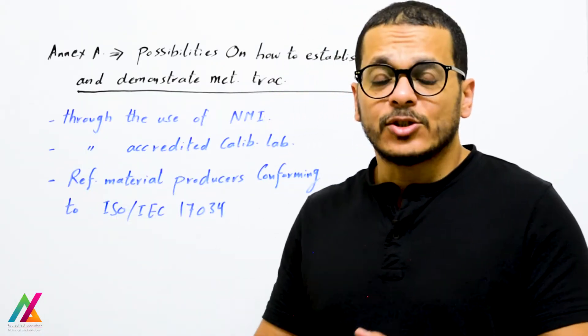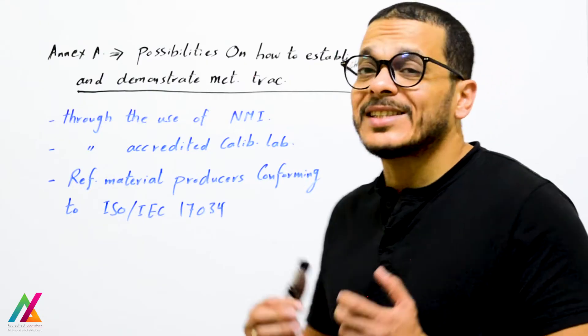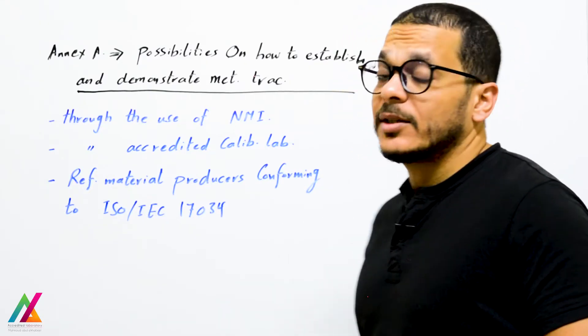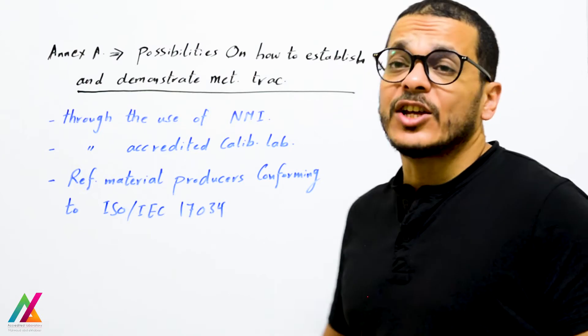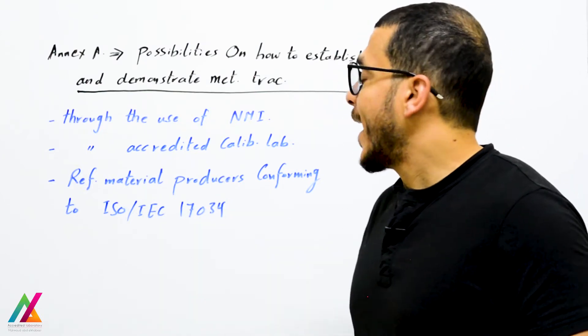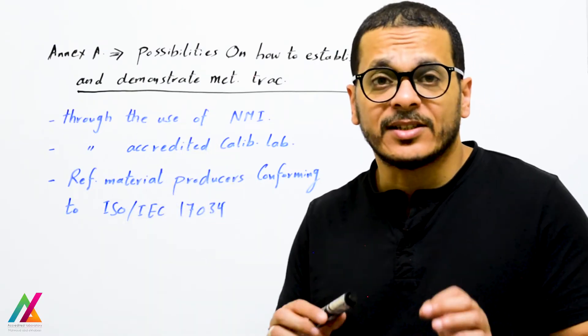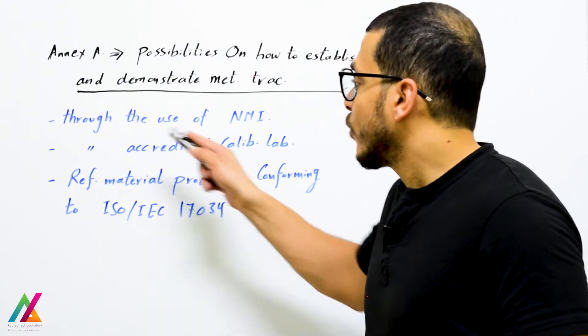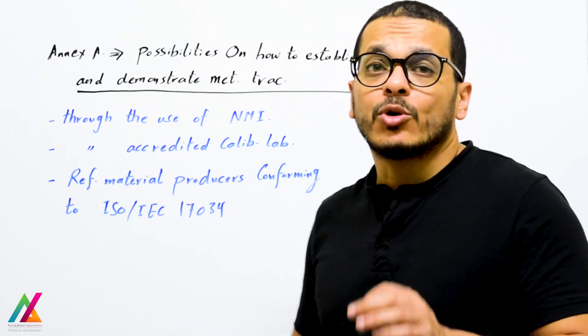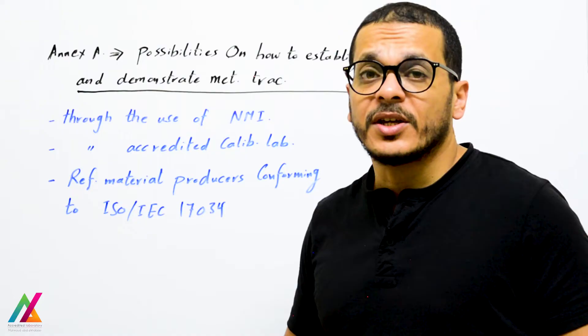In Annex A of this document you will find possibilities on how to establish and demonstrate metrological traceability — through the use of the national metrological institute and through an accredited calibration lab. Also, certified reference materials (CRM) from reference material producers shall conform to ISO/IEC 17034.